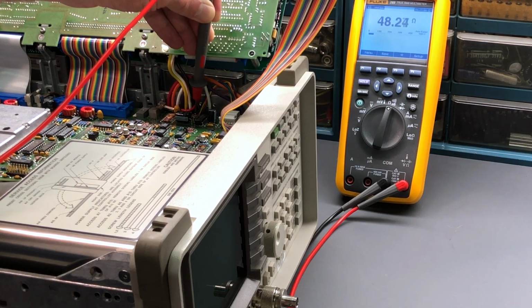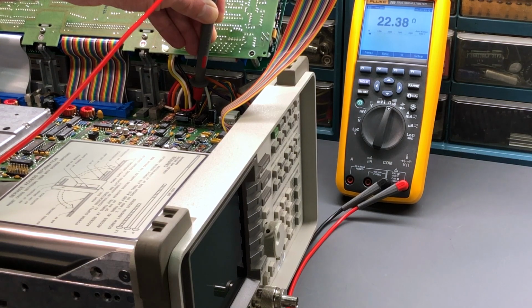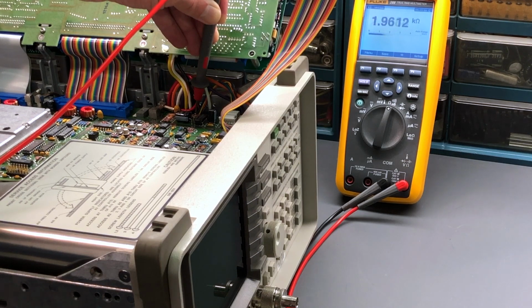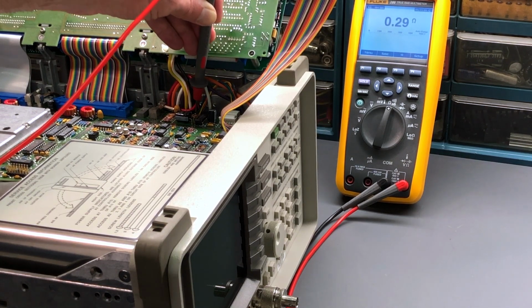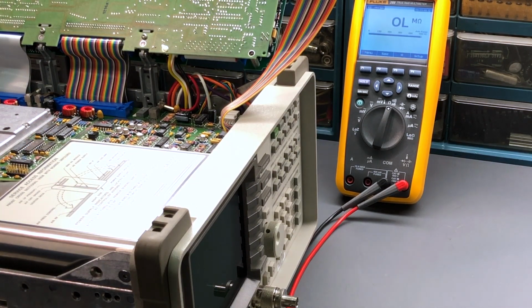Remember that when this is down at that low resistance, 22 ohms or so, it's basically pulling that audio line down towards ground with very low resistance. When you get up, let's say over here, to a little over 1.6 K ohm, that's where you'd expect the audio to get very loud. But that would be ear-piercing loud, if not destroying the speaker, given how it's operating. So again, when it's all the way down there, 0.3 ohms, no problem. That's basically shorting the audio line to ground. All right. So I think we can safely say that the potentiometer is functioning properly, that there's no issue with that. So I'll go ahead and power up the spectrum analyzer.